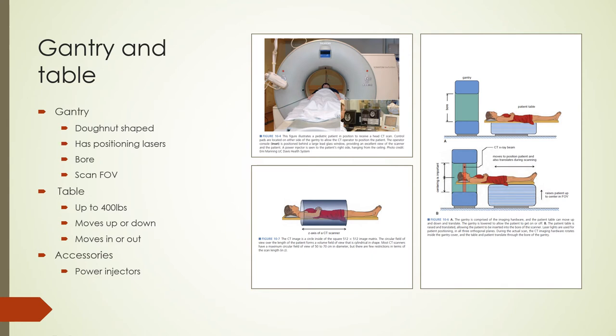Modern CT scanners have a donut-shaped gantry equipped with laser lights and button controls to raise and lower the patient table and move it in and out of the scanner. The controls are also available to the operator in the control room. Patient tables can support up to 400 pounds, though higher-weight-limit tables are available. The scan field of view is a circular region in the x-y plane, between 50 to 70 centimeters in diameter, with the z-axis parallel to the cranial-caudal direction.